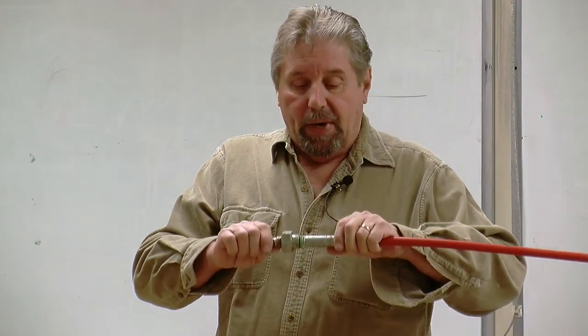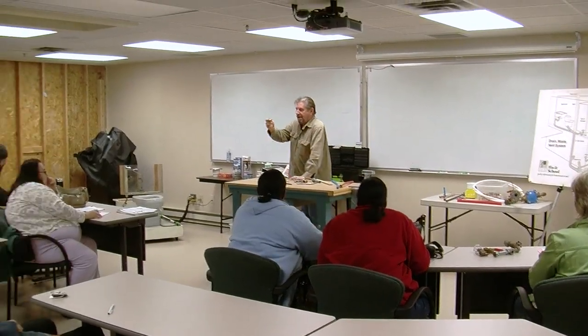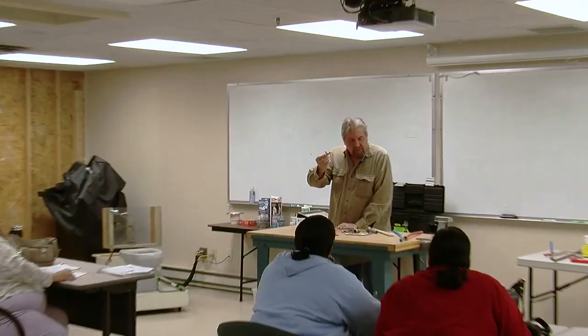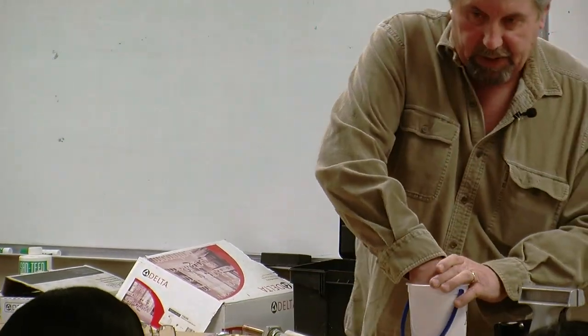Pretty much like the corrosion piece that we passed around. So what you can do is install what they call a dielectric fitting. This fitting is made so that these two pipes don't touch, yet it's waterproof, okay? They're about 15 or 20 bucks. They're barbed fittings, okay? And so what you do is you simply slide the pipe on, and put on a clamp. It looks like a ferrule, but basically it's a clamp.